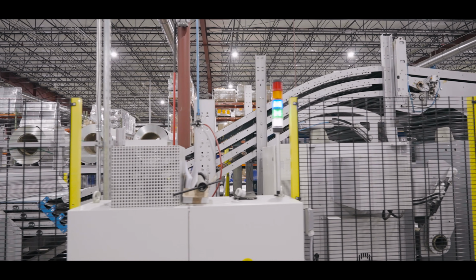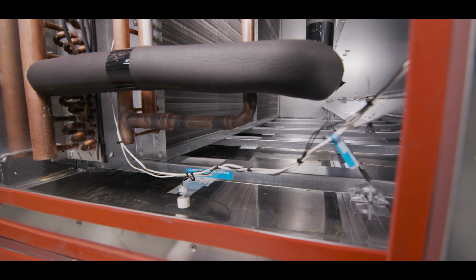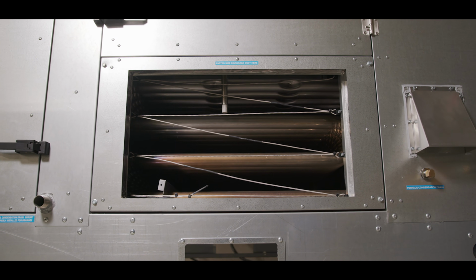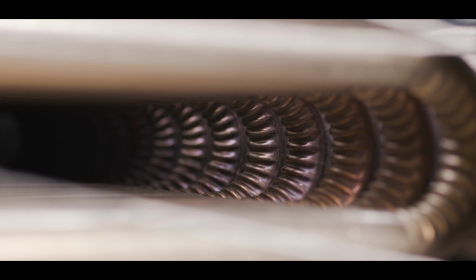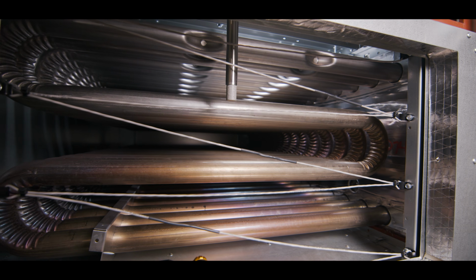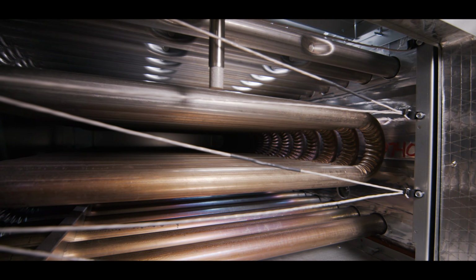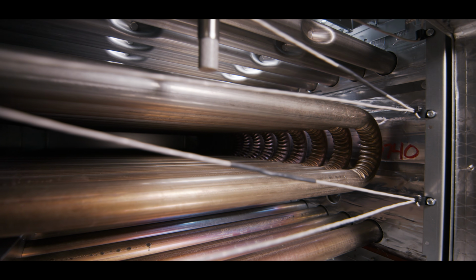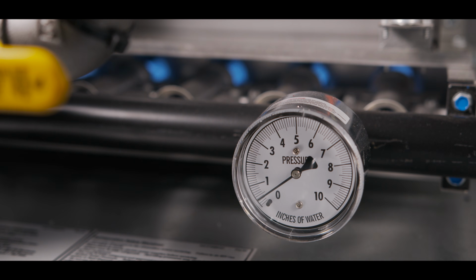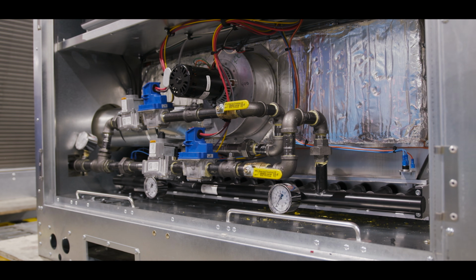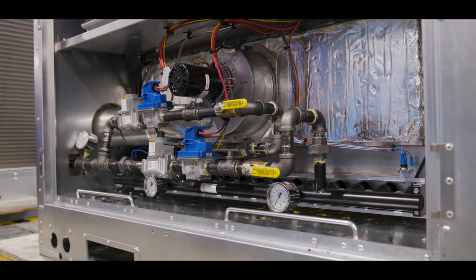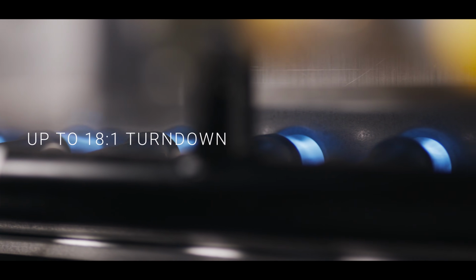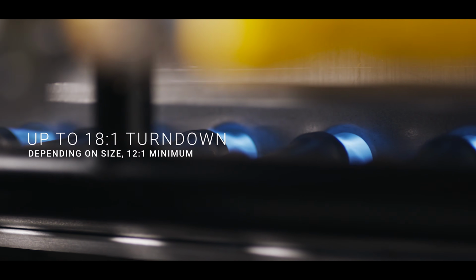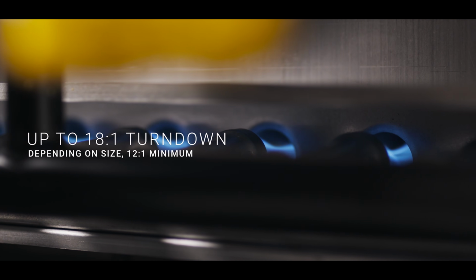Stainless steel is another material we use more selectively, like for our drain pans or our heating coils. In most RTUs, these are usually made of aluminized steel, which works but can corrode over time, allowing rust to take over. With a unit meant to last 20 plus years, stainless steel is just the way to go. And while we're here, it should be no surprise that our heating manifolds all modulate, and we even offer a split manifold design, which allows for extreme turndown ratios to deliver a precise discharge without having to cycle the heat on and off when demand is low.